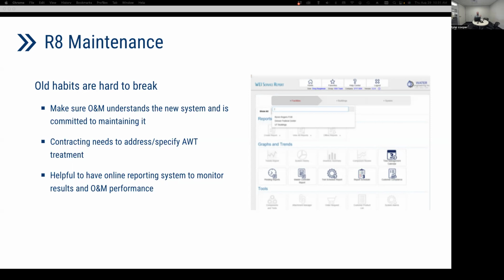So within that, specify within the O&M contracts how they are maintaining those alternative water treatment assets as part of the contracts. Second, again, have some type of online reporting system to monitor results and O&M performance. We should be getting reports on a monthly basis, and training your building teams to understand what parameters they're looking for in those water treatment reports allows for that quality control check to make sure the systems are operating optimally.